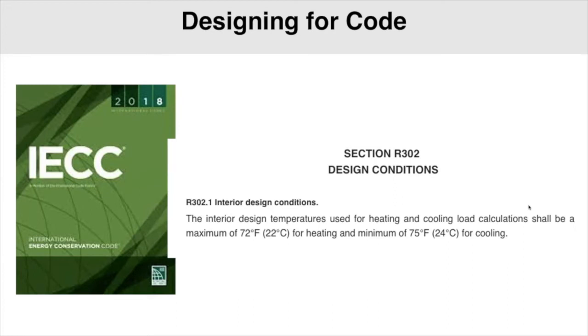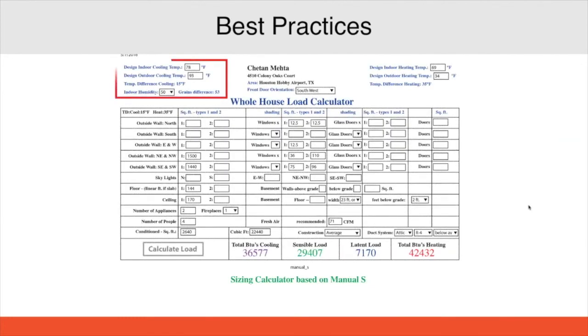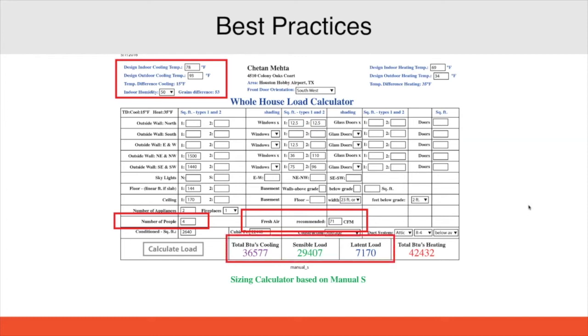You have to follow the Manual J and the code guidelines. So our best practices: we've got an indoor design cooling temp of 78. We've got our outdoor design temp of 96, 50% relative humidity, 4 people inside. Our ventilation rate is 71 CFM, and this is going to tell us our sizing for this system is going to be based on 36,000 total BTUs of cooling, and then it's going to give us our sensible load and our latent load.